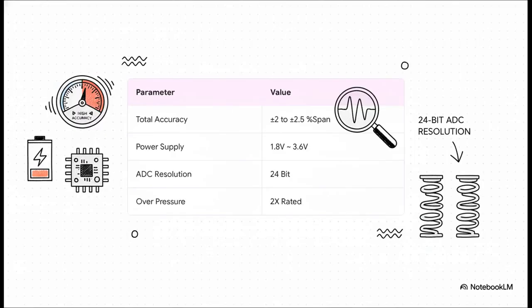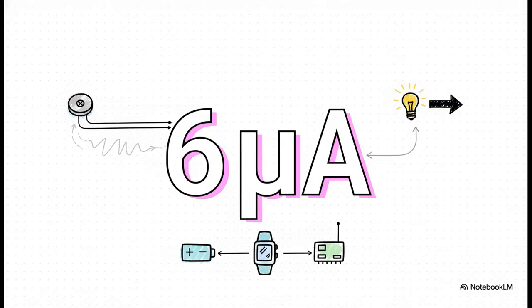And that internal design translates directly into some seriously amazing performance. Just look at that 24-bit ADC resolution—that means it can tell the difference between over 16 million different levels of pressure. That's the kind of incredible subtlety that allows a ventilator to deliver the perfect breath. Oh, and it's tough too. It can handle sudden pressure spikes up to 2 times its rating, so it's reliable even when things get a little chaotic.